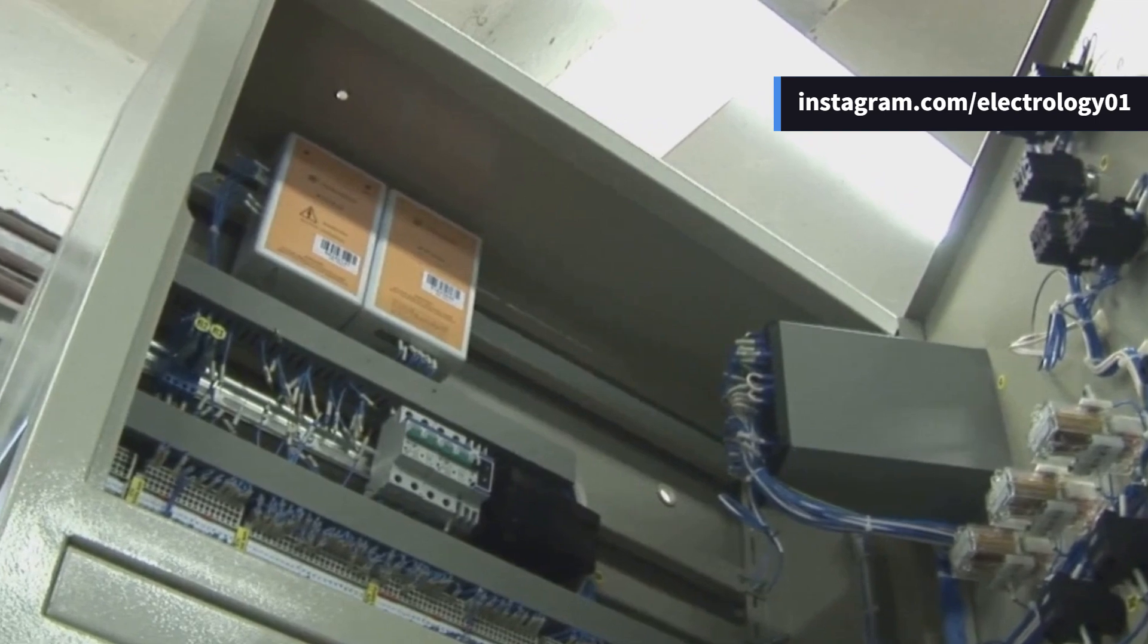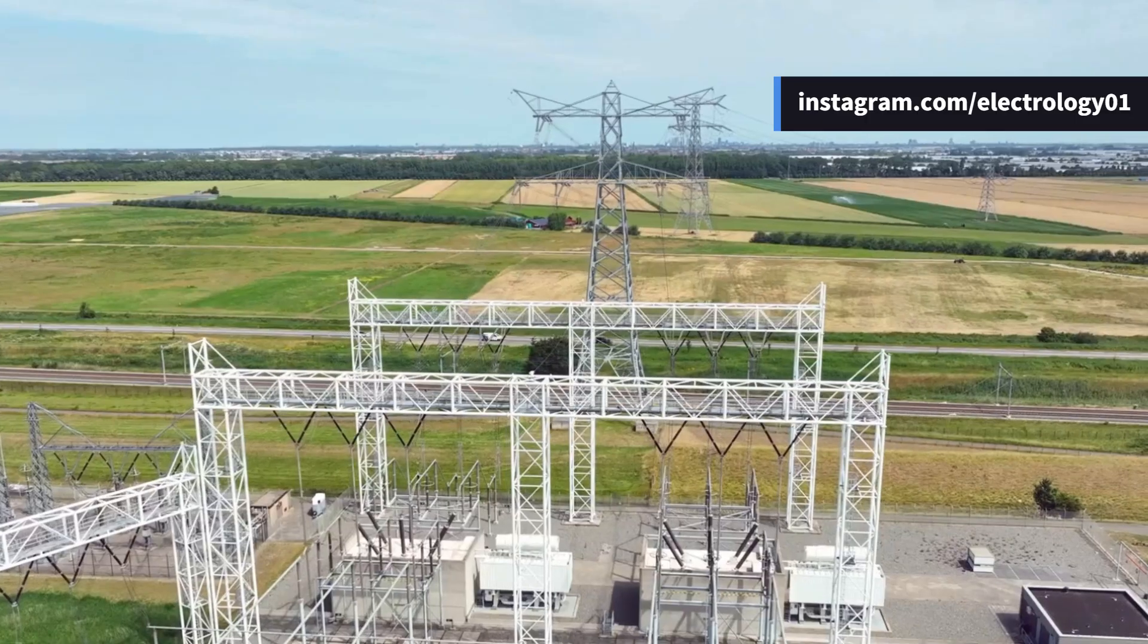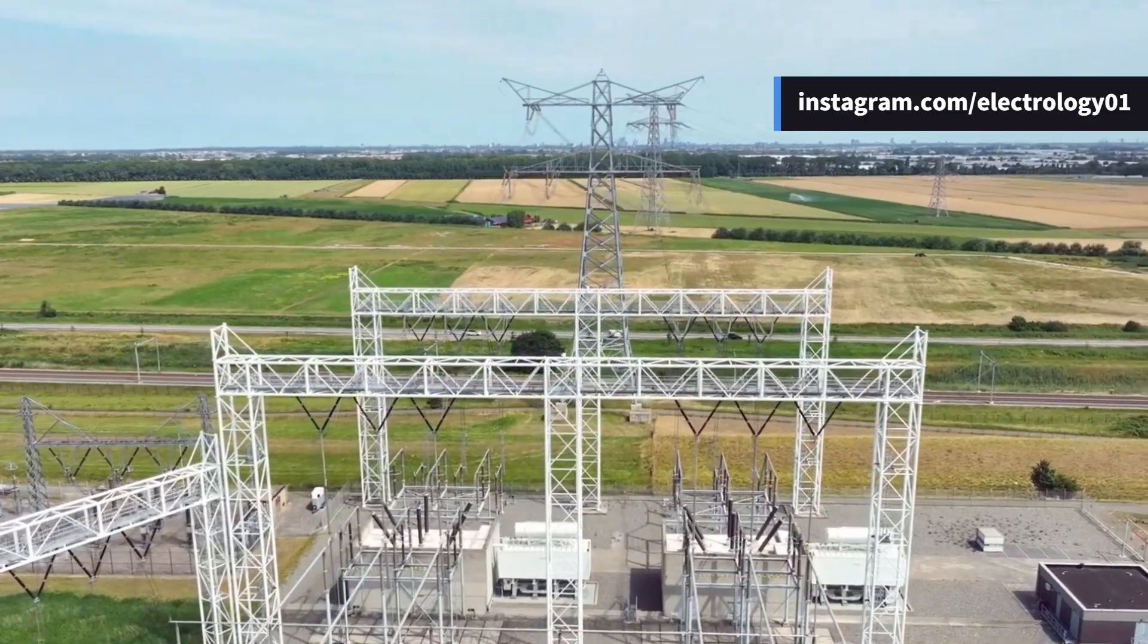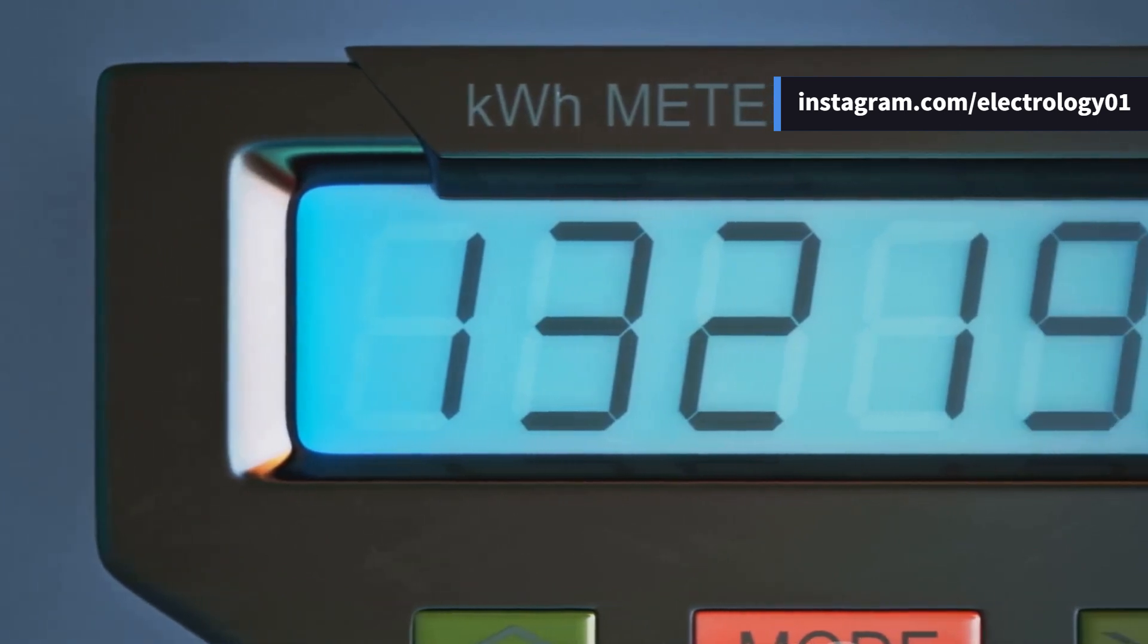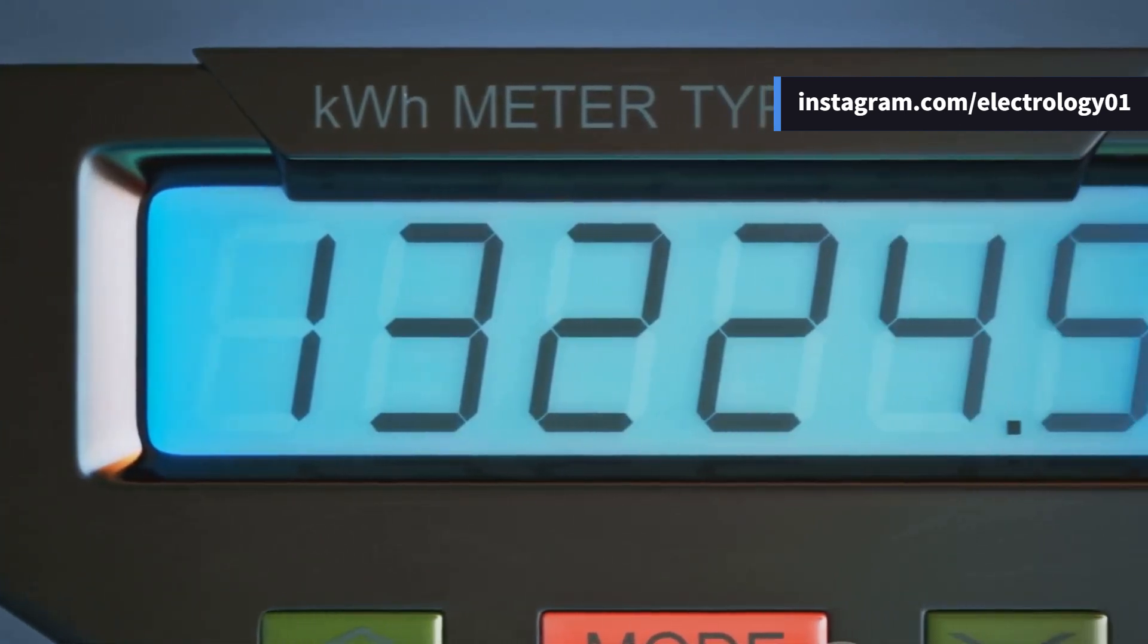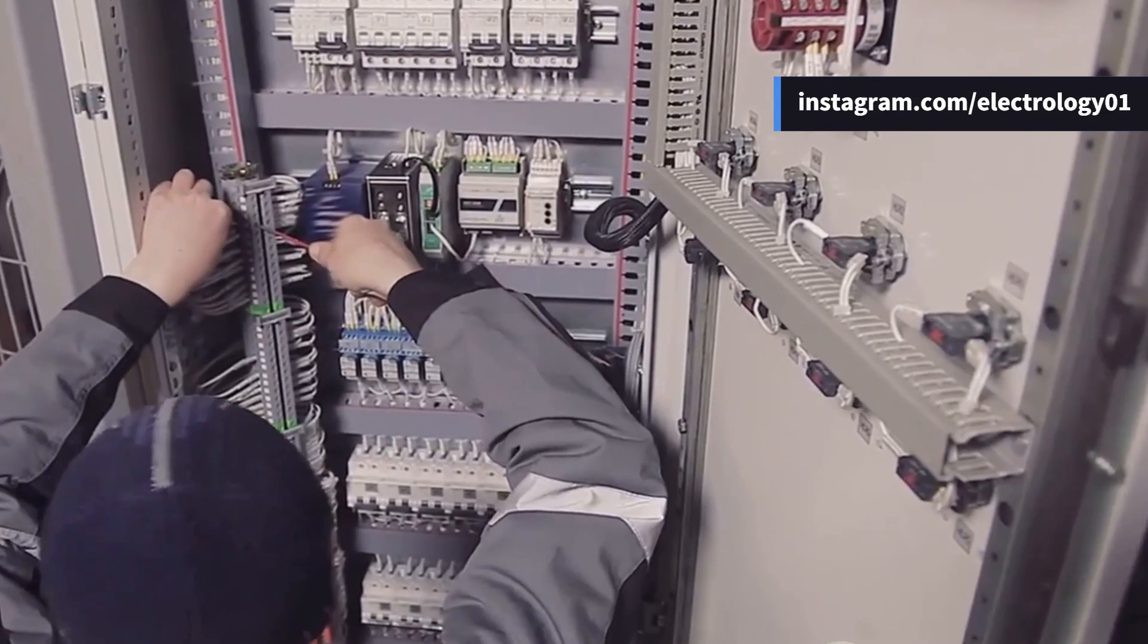So it's clear why protection CTs must be used for relays to ensure reliable fault detection, and metering CTs must be used for accurate energy measurement under normal conditions. Always use the right CT for the right application to maintain system reliability and avoid costly damages.